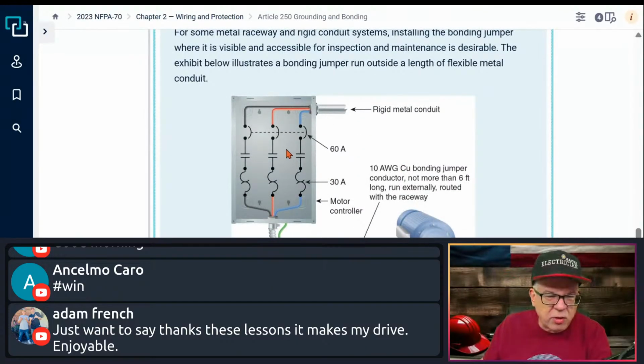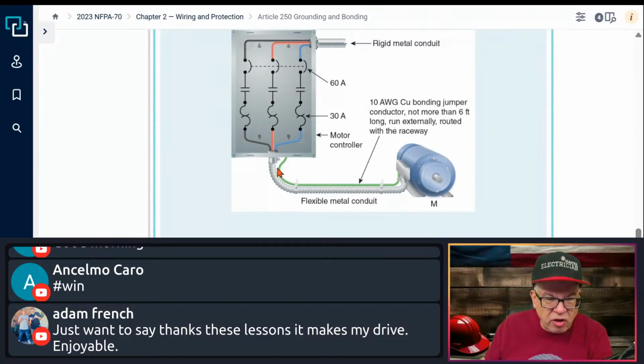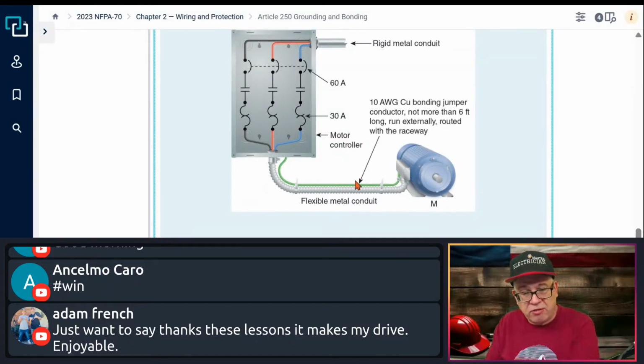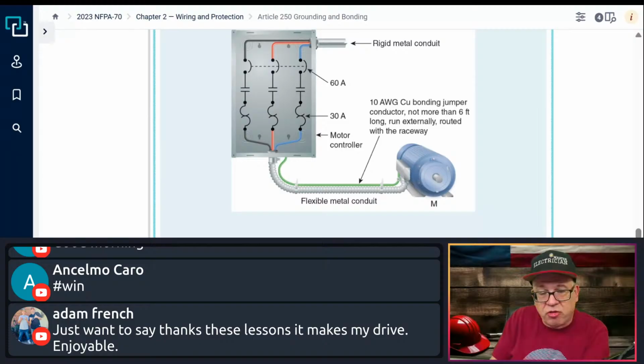So here it's coming into the piece of equipment, right? Motor controller, and now it's going out to motor. In this case right here, it's using flexible metal conduit, okay? So it says 10 AWG copper bonding jumper conductors, not more than 6 feet long, run externally routed with the raceway. Okay. So if you see right here, this is what it's talking about. This is a load side application, right? This right here is running external. It is permitted as long as it's run with it. And can it be strapped to it? Yes, it can, because it's associated with that circuit, okay? And so this is not to be run separate.